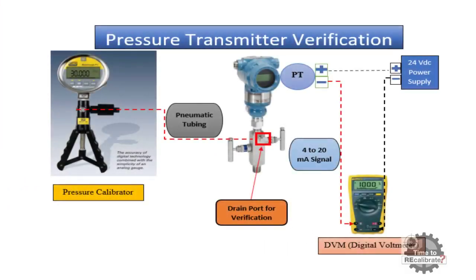Positive terminal of pressure transmitter gives 4 to 20 mA analog output. So, connect a digital multimeter in series with pressure transmitter to measure analog output. In other words, put the multimeter in milliampere measuring mode, and connect the red probe to the plus terminal of pressure transmitter and connect the black probe to the negative terminal of the 24-volt DC supply. So, everything is now set for verification of pressure transmitter.